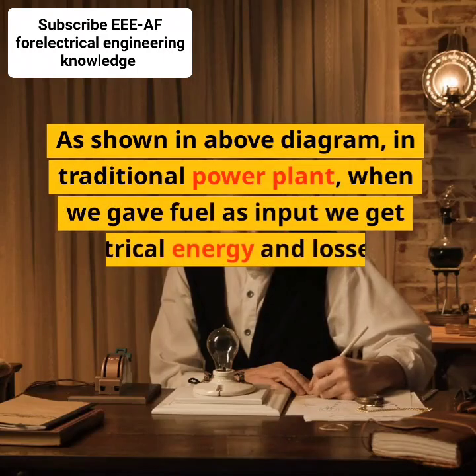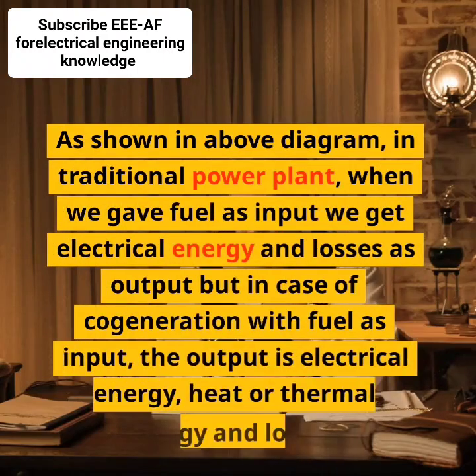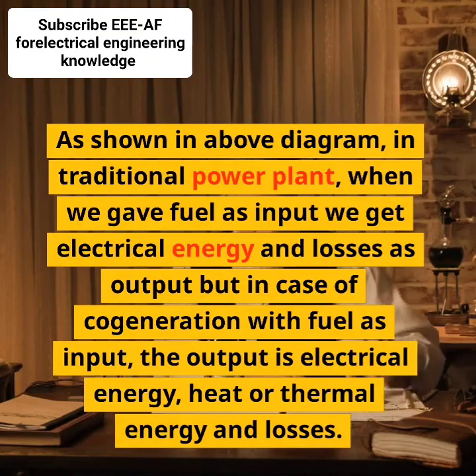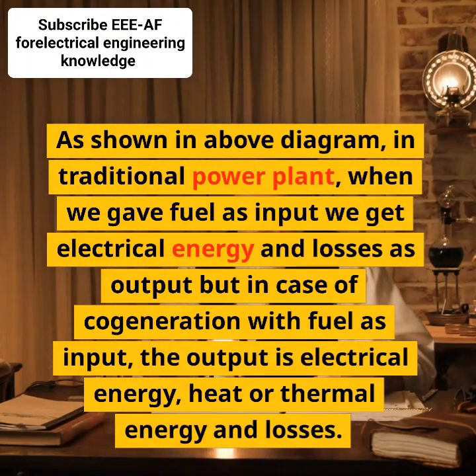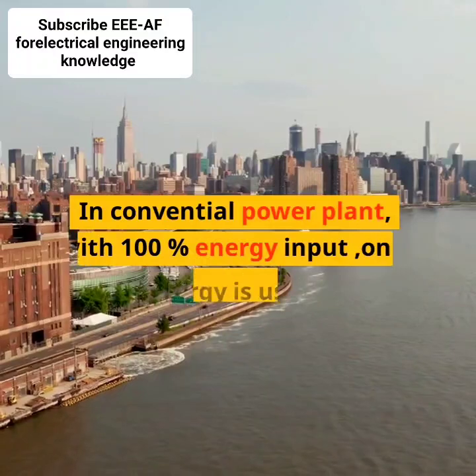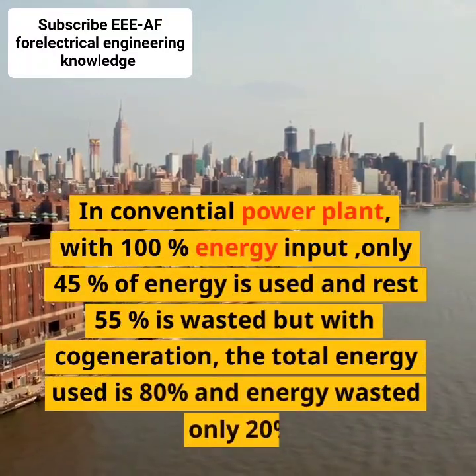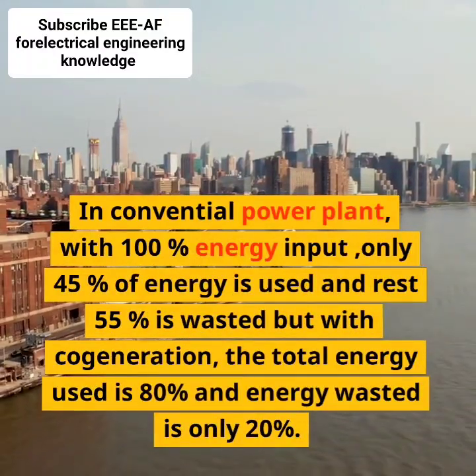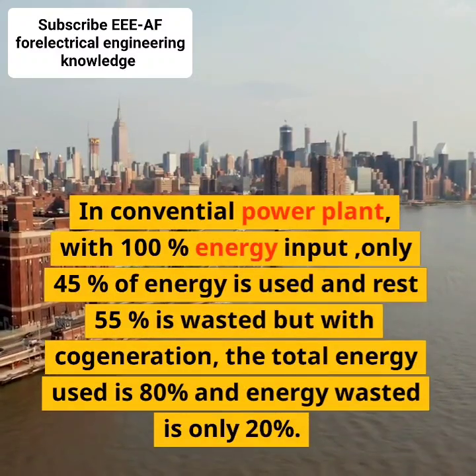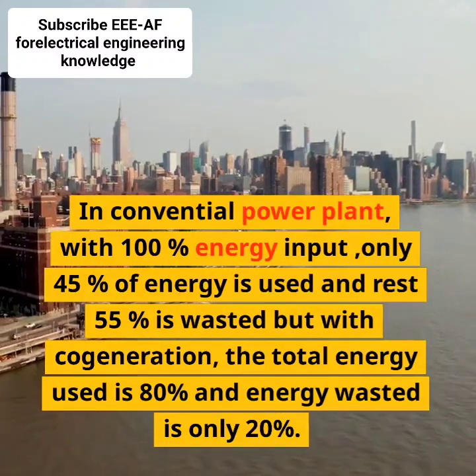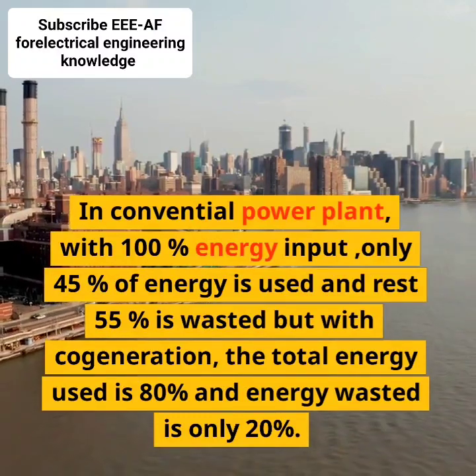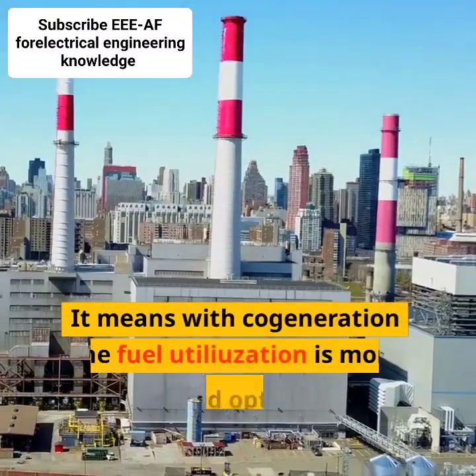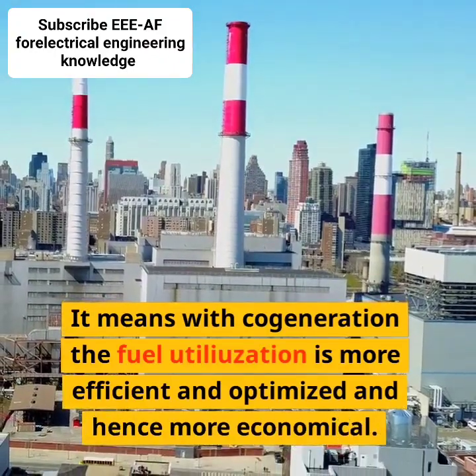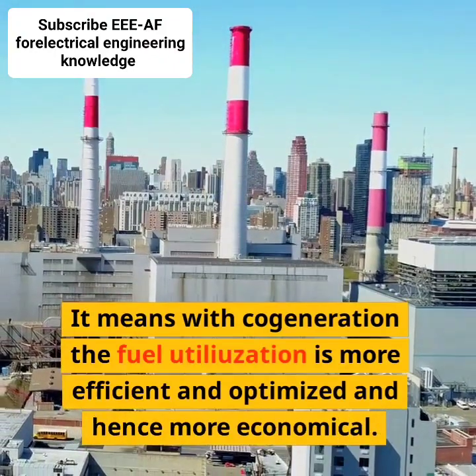As shown in the above diagram, in a traditional power plant, when we give fuel as input, we get electrical energy and losses as output, but in the case of cogeneration with fuel as input, the output is electrical energy, heat or thermal energy, and losses. In a conventional power plant, with 100% energy input, only 45% of the energy is used and the rest, 55%, is wasted, but with cogeneration, the total energy used is 80% and the energy wasted is only 20%. It means with cogeneration the fuel utilization is more efficient and optimized and hence more economical.